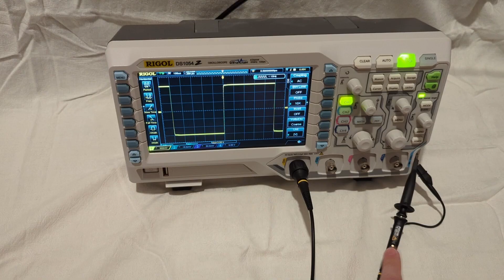And then I want to adjust this in the horizontal range where I'm getting about 1 period on the screen. So that's this knob, and we're just going to turn that until we get about 1 period on the screen. So now we can see it pretty well. And on this particular scope, the compensation is on the end of the probe. Not all scopes are like this. Sometimes they have the compensation up here at the other end of the probe.